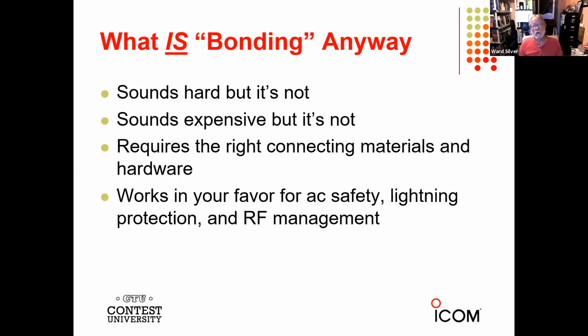But it does require using the right connecting materials and hardware so that the bond stays in place. This is particularly true when you're working outside and you have buried conductors or ground rods, or you're bringing things in and out from outside. When you bond your equipment together, it works in your favor for all three areas that we have requirements for: AC safety, lightning protection, and RF management. So by an effective bonding program in your station, you're going to solve a lot of problems or keep them from happening in the first place.